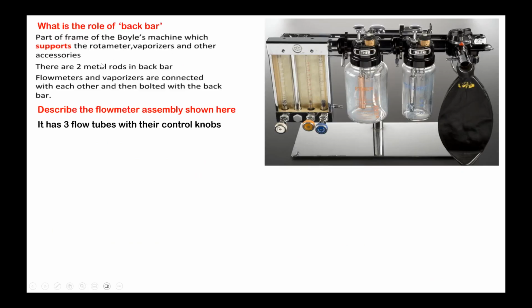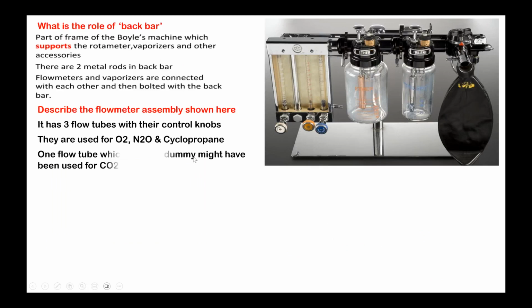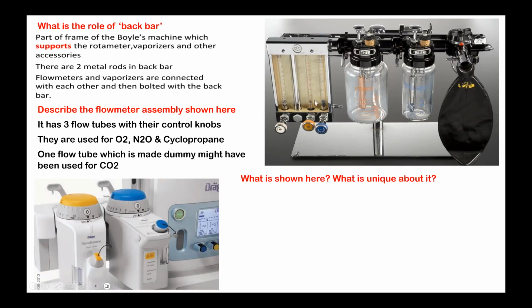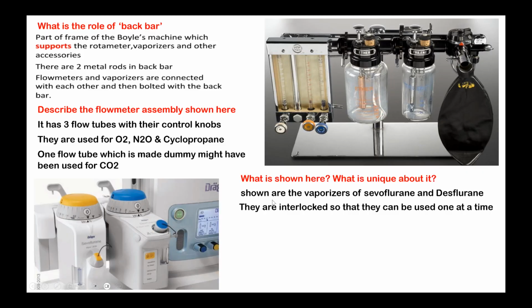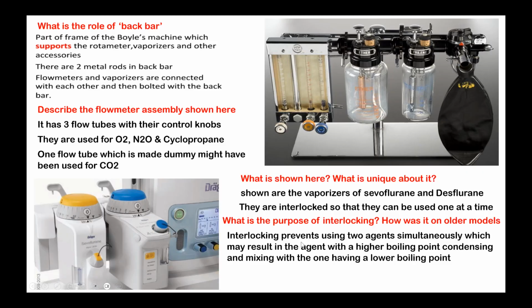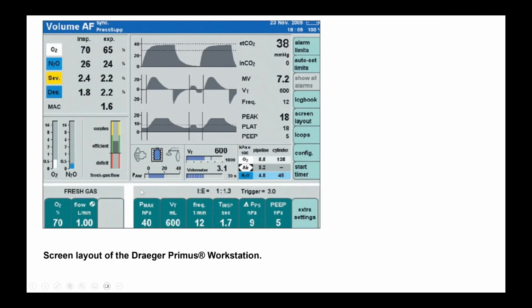The goal is to mount all the vaporizers. Newer machines have what is called the interlocking system. In earlier machines you could use both vaporizers at the same time, but modern machines have the interlocking system, which won't allow the operation of two vaporizers at the same time. The purpose of interlocking is that two agents cannot be opened together. So that is new.